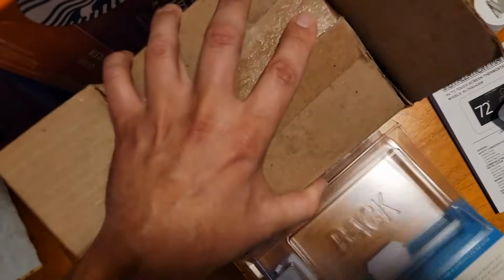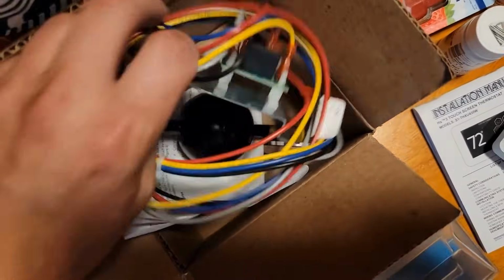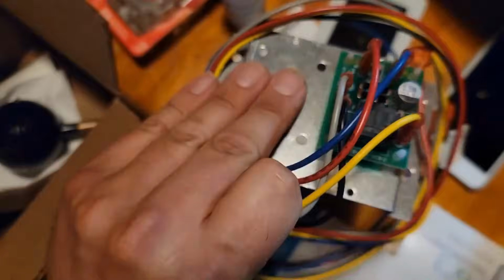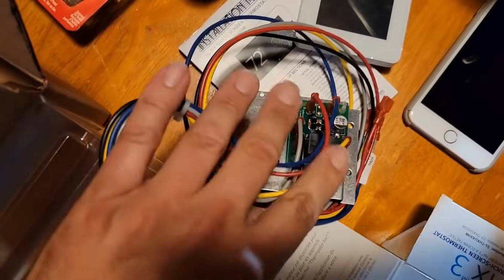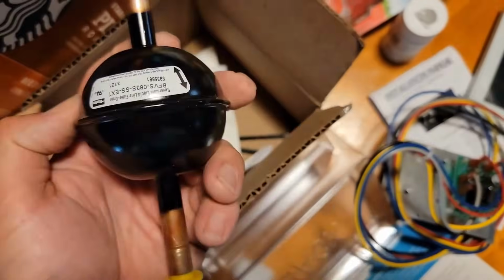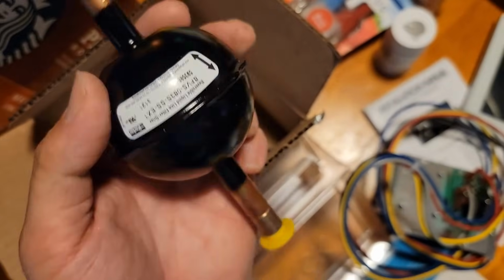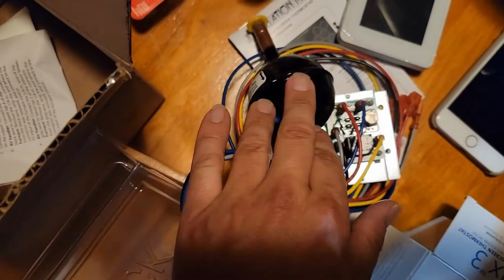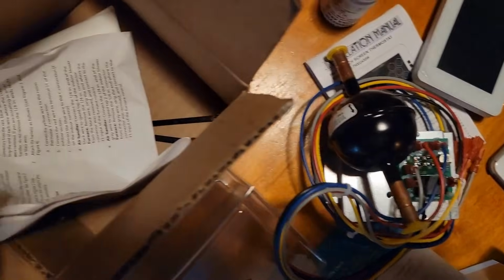This right here is an installation kit that I had to get with the HMH7. I'm trying to see, does it say anything on the box about installation kit? No, it doesn't. It just comes as a box here. And this box includes this relay board here with some wiring, and then this filter dryer. Definitely need this filter dryer. This is a bi-flow filter dryer that's installed at the outdoor unit section in the liquid pipe.